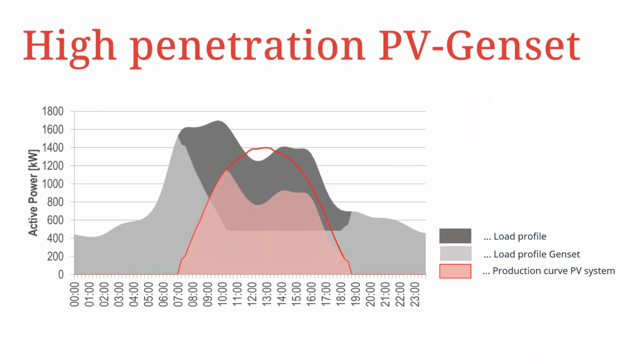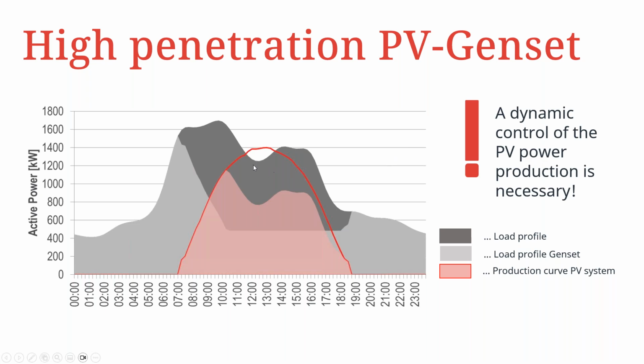In a scenario where you have a high PV penetration, this is where we have a high volume of PV installed in the system. In some cases, as you can see from this power curve, the PV curve, you could have the PV just summing up to or just above the load demand. So it is absolutely necessary for us to have dynamic control of the PV, because if this is not applied, then we would have damage to the genset or the inverters installed. There's a high possibility of the genset being turned into a motor, or basically having a negative feedback. So these are scenarios that we need to have control over.